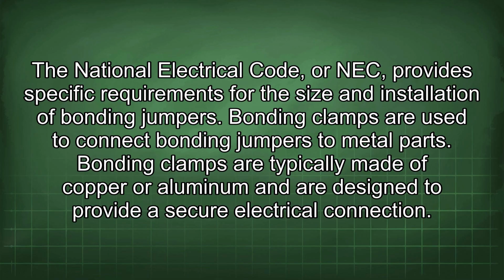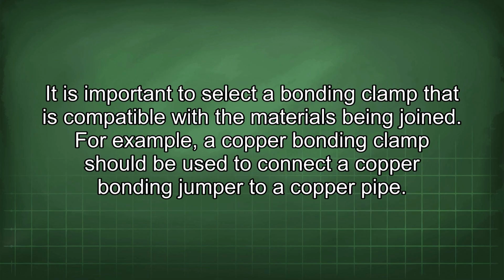Bonding clamps are used to connect bonding jumpers to metal parts. Bonding clamps are typically made of copper or aluminum and are designed to provide a secure electrical connection. It is important to select a bonding clamp that is compatible with the materials being joined. For example, a copper bonding clamp should be used to connect a copper bonding jumper to a copper pipe.